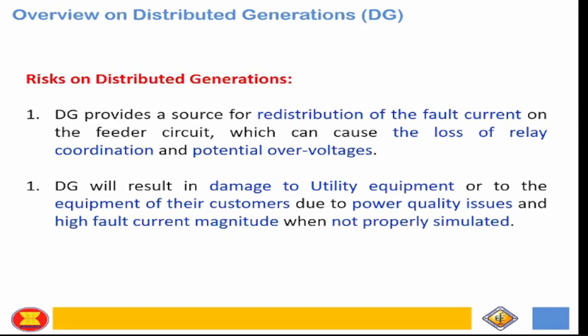And the potential overvoltage. When does the overvoltage occur? The overvoltage will occur if the interconnection transformer of your distributed generator is an ungrounded system, and it will happen when it's disconnected and isolated from the distribution system. Then we all know the principle of line to ground fault: in an ungrounded system, the healthy phases will have overvoltage. We will discuss that later.